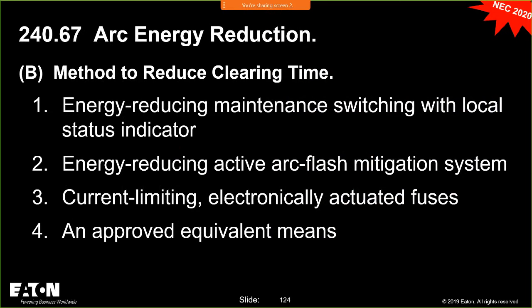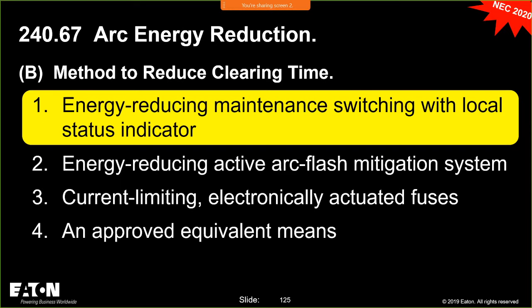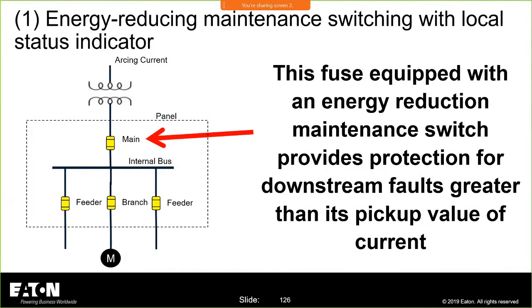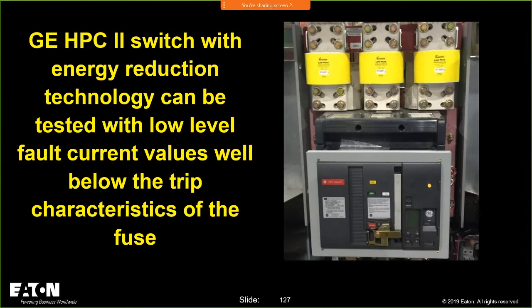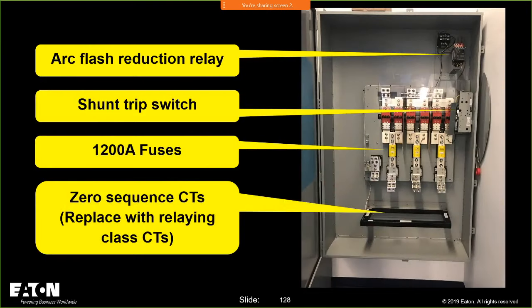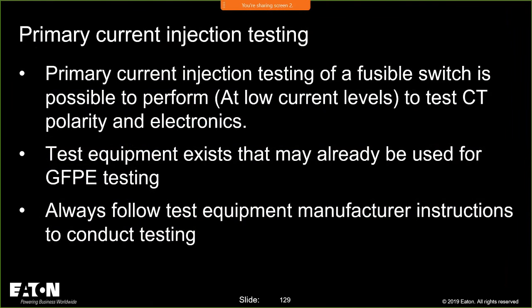So if you're doing the energy reduction maintenance switch with a local status indicator, that's the switch that's going to be doing the job. The GE HPC II switch is one example of a device that'll help you. This is the Eaton switch that has a disconnect and a shunt trip, 1200 amp fuse, zero sequence CTs. We've got solutions coming out every day on this type of thing. We have tools that you're going to be using to help you determine when to employ technologies.